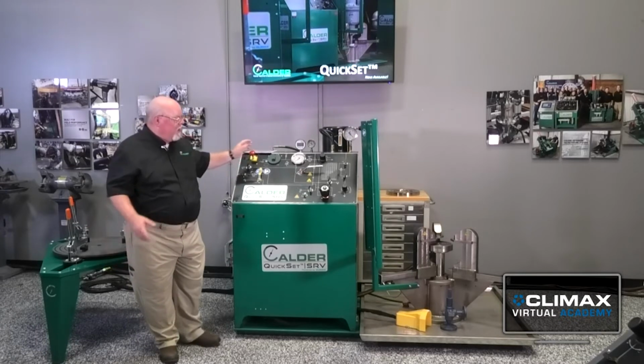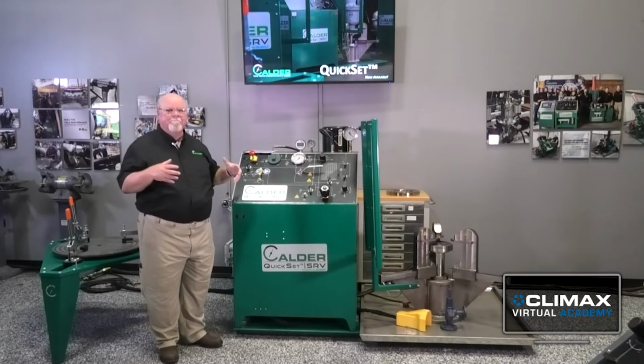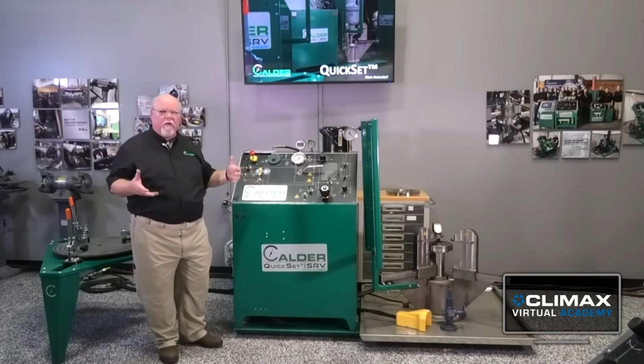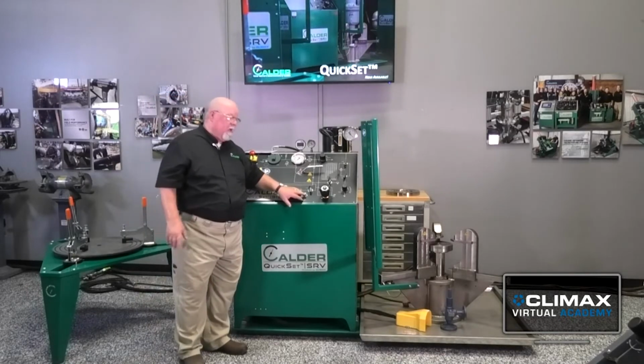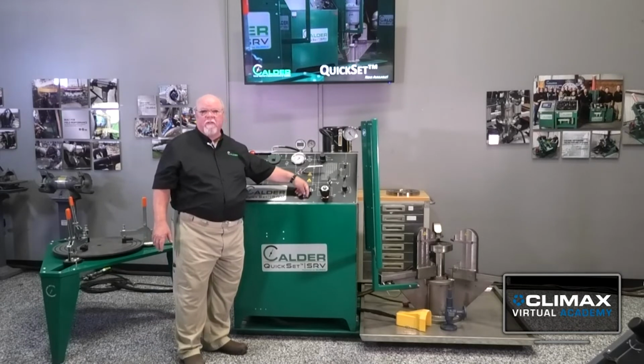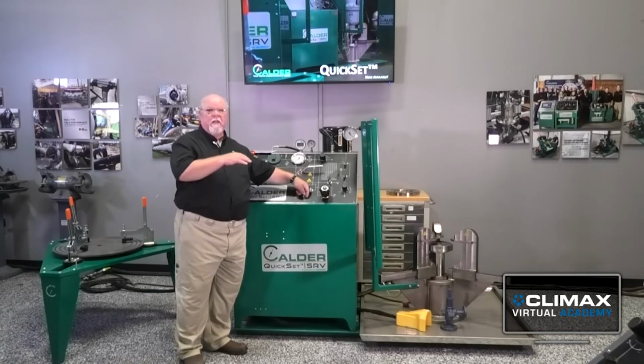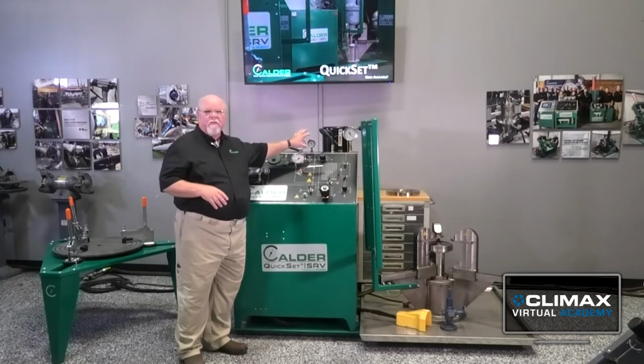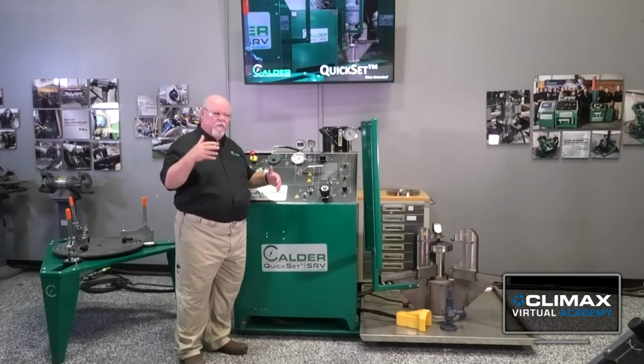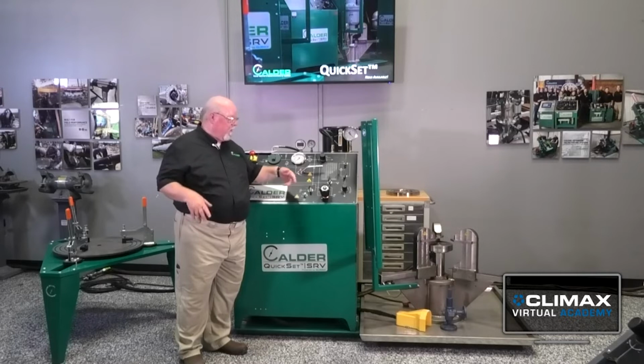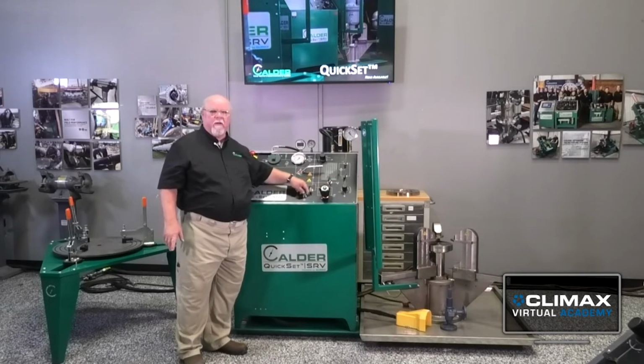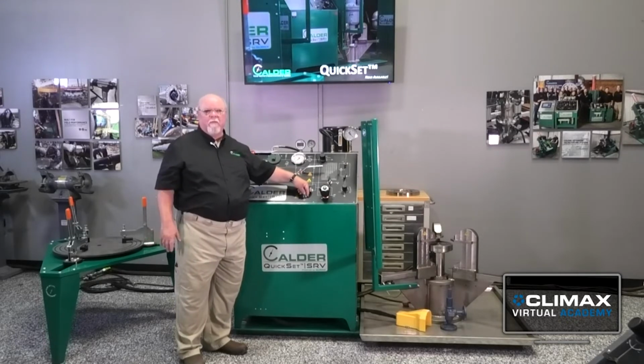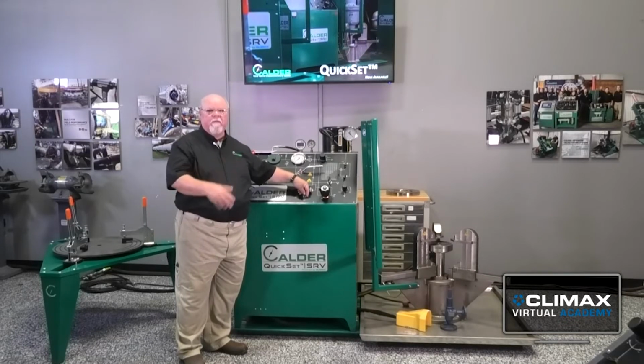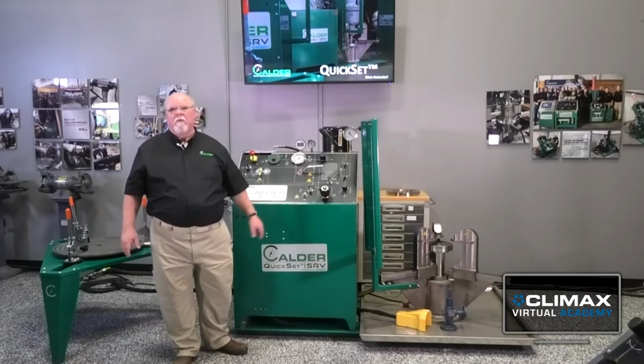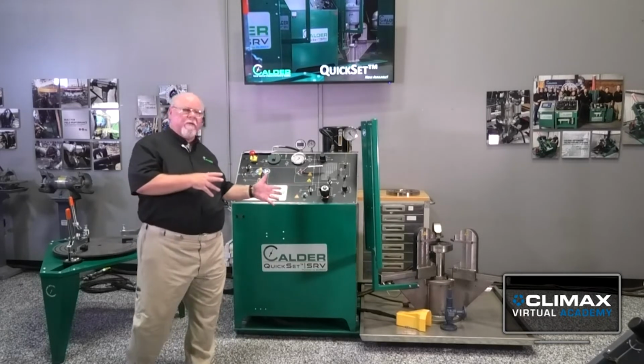For our test stands, we can't allow the valve to be tested without what we call an operator presence switch. In this case, it's a button that has to be pressed in order for me to take what stored pressure I have and go to the test valve. So in order to run the test, as I'm adjusting my regulator, I have to have this, we call it an operator presence. So you have to be here to be able to make the test run. So those are standard product as it comes.